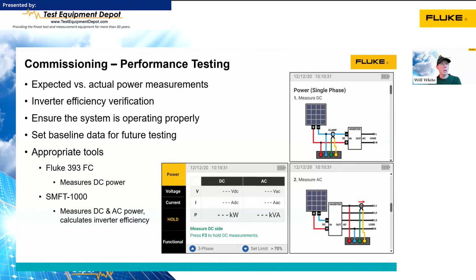We do have some tools that can measure power. The 393 clamp meter can measure DC power. You'd have to calculate the AC power measurement as well. The SMFT 1000 can measure DC power, and then it can measure AC power, and will actually calculate inverter efficiency automatically. It can test up to 60 amps, and the caveat being that you need to be able to get the current clamp that comes with the meter around all of the DC positive conductors. So you got to be able to fit them all in the DC clamp. Now, same thing on the AC side, you need to be able to get that clamp around one of the legs of the AC output.